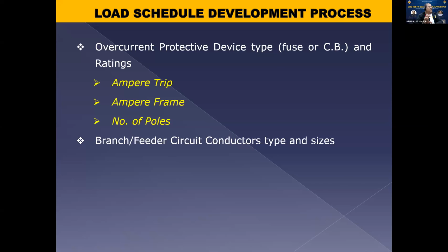Kasi ang value ni ampere frame is if you have circuit breakers na within the range dun sa ampere frame niya, kasi yung ampere frame is ranges of the sizes of circuit breakers yan, physical size. So usually yung mga 20 ampere, 15 to 50 ampere na circuit breakers, yung ampere frame nila is sa 50 amperes lang yan. Limit, maximum.